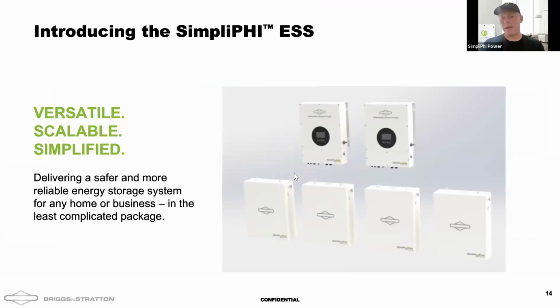These two are going to communicate intelligently, and then what you're not seeing here, which would come with a system, is a gateway. So you'd have a gateway which would take all the information from that inverter and from the batteries and upload it to the mobile application where you can program your system, monitor your system, remotely change settings, check for firmware updates and push firmware updates over the air, check on fault codes and warning codes, all these things that you can do without even leaving your home to actually drive to the customer's site.